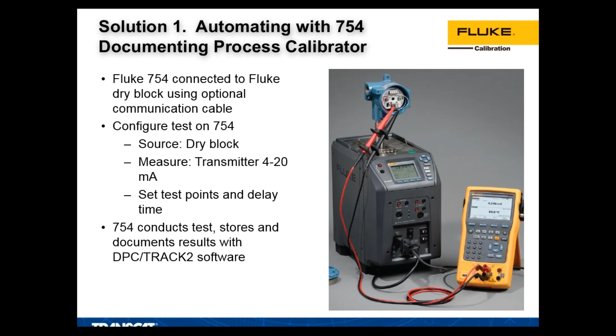So first off, let's answer the question of why is a dry well even required? Many of you may already be using the 754 to perform temperature calibration, never used a dry well before, and wonder what is the reason we'd even need a dry block. So when you're simulating a thermocouple or RTD or sourcing the voltage or resistance from the 754, one of the things that you're doing is neglecting the temperature sensor. You've actually disconnected it from the circuit. You're just focusing on whether or not the transmitter is reading correctly. Sort of assumes that the temperature sensor must be perfect.